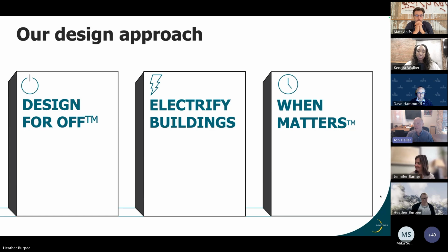Design for off really mirrors the VHE HVAC system approach that Dave introduced at the beginning, focusing on reducing the loads as much as possible so we can have smaller, simpler systems that we can cycle off when they're not needed. The electrified buildings component is to prioritize efficient heat pump systems in lieu of burning fossil fuels whenever possible. And then when matters relates to creating flexible loads in buildings, because to integrate with the developing grid, as it relies more and more on solar and wind, when we use energy starts to matter as much as how much we use.